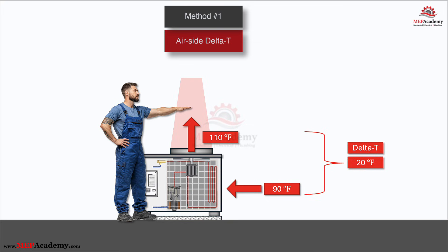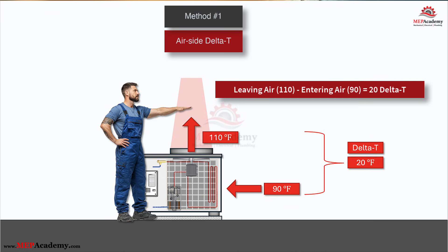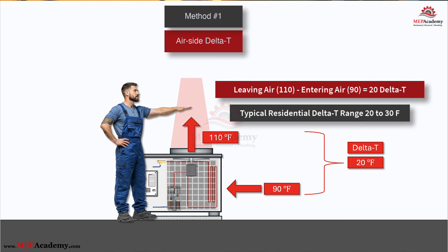You stick a thermometer in the ambient air going into the coil, then stick it in the hot air blowing out the top. If the air entering is 90°F and the air leaving is 110°F, your delta T is 20°F. Leaving air minus entering air — most residential units equal 20 to 30°F rise. Takes 30 seconds, zero tools except a thermometer. This measurement tells you how much heat the condenser is rejecting into the atmosphere. It's an airflow and heat rejection performance measurement, not a refrigerant side measurement.